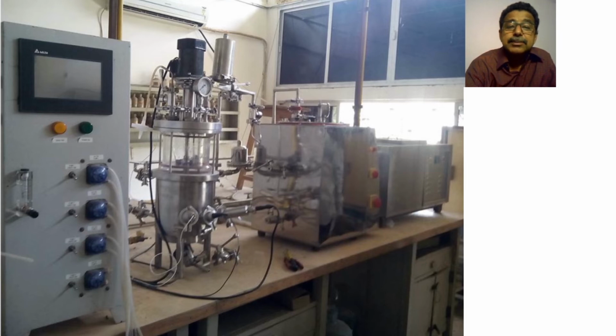For anti-foam, suppose foaming is produced and the foam reaches the top flange, where one sensor is kept, called the anti-foam sensor. The wire is connected with the control unit, so it will give a signal that foam has touched the sensor. Immediately the PID control will start the anti-foam peristaltic pump, and anti-foam oil is added dropwise in the vessel, so that the foam may subside. When the foam subsides, the signal of the anti-foam electrode stops, and this PID will stop the addition of anti-foam oil. So it is also controlled automatically, and a fermentation run lasts for 7 days, 8 days, 10 days, whatever, depending upon the product and the organism manufacturing it. Till then the pH is controlled, the temperature is controlled, and the anti-foam agent is there. And the last peristaltic pump, the fourth one, is used for addition of feeding material or nutrient addition.